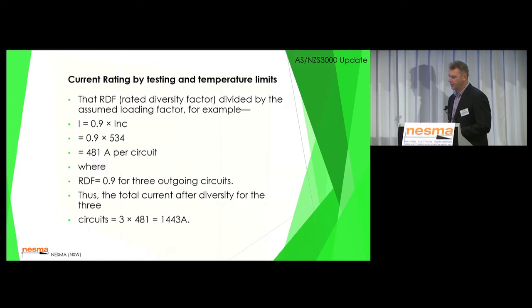So the rated diversity factor divided by the assumed loading factor. So here we have a rated diversity of 0.9 in this calculation. This is the example in the standard that you can refer to. 0.9 times 534 amps, which is the derated rating of that circuit, gives you a total rating of 481 amps per circuit. And that's giving us a 0.9 rated diversity. Now, if we've got a 1600 amp switchboard in this situation, we can pull our rated diversity up a little bit. We can't go past our nominated rating or a derating of our circuit breaker.